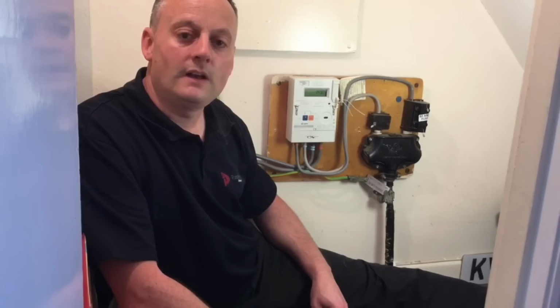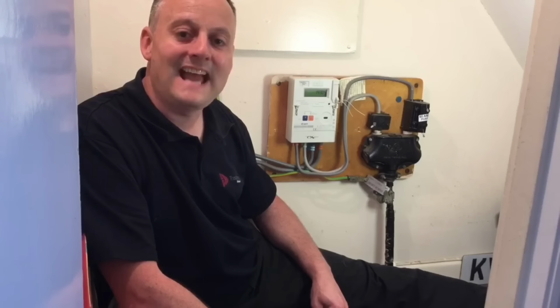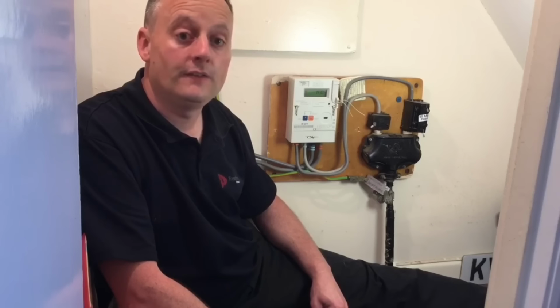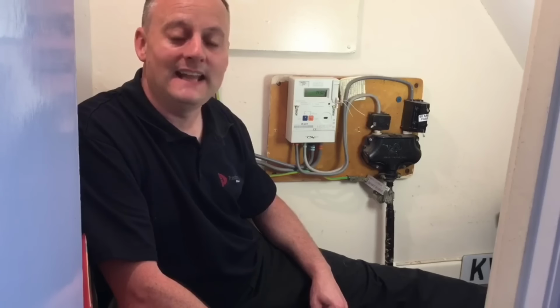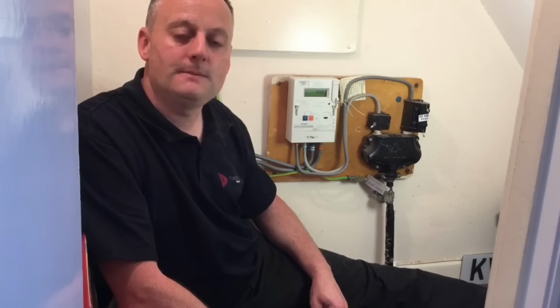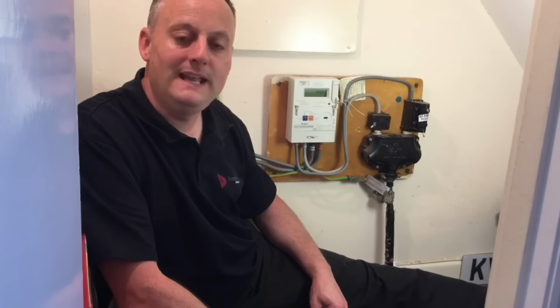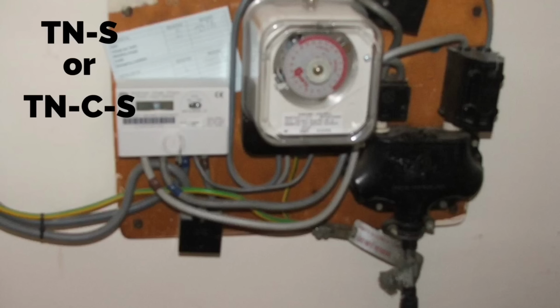We will see later on in our learning at college that the TNS, the terra neutral, the earth and neutral, are separate. TNS earthing arrangement has a maximum external earth fault loop impedance of 0.8. So when we turn up an installation, possibly the first thing we're going to do is look at the mains end to determine the earthing arrangement, the size of the incoming fuse, and the size of the tails and earthing conductor, whether they're a TNS earthing arrangement or a TNCS earthing arrangement.